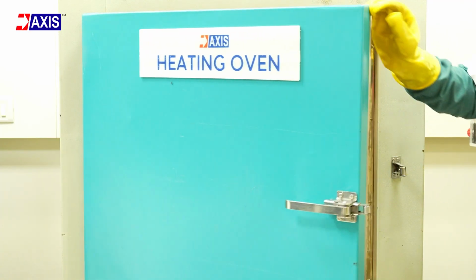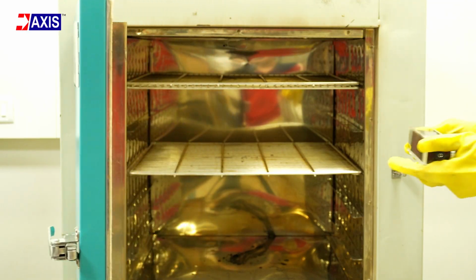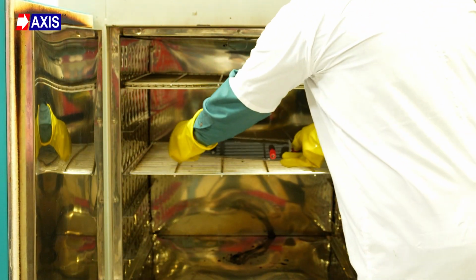Every type of earth-enhancing compound manufactured at Axis is tested and certified for key performance benchmarks. These include resistivity tests to confirm how well it reduces resistance, leaching tests to ensure no harmful chemicals escape into the soil, and corrosion tests to check that it won't damage nearby conductors.